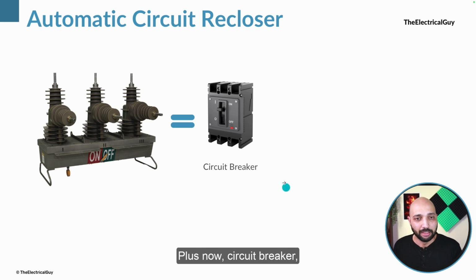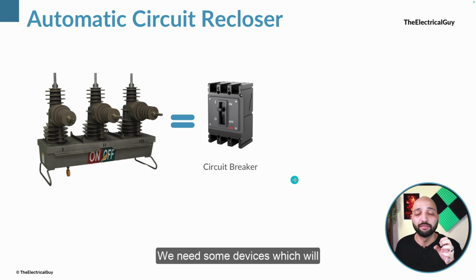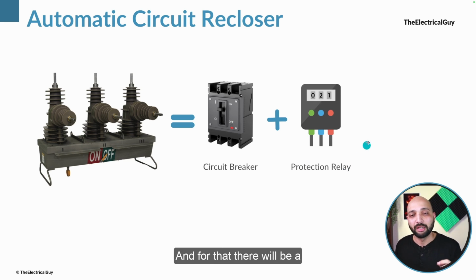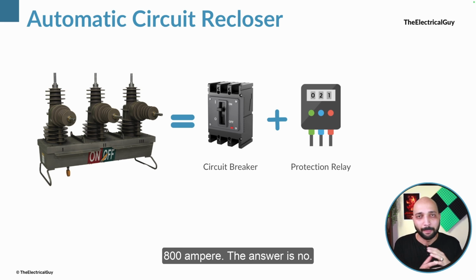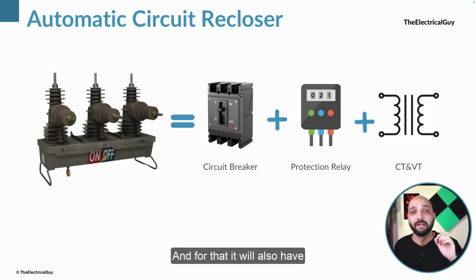Plus, now circuit breakers, are they capable of sensing the abnormal condition on their own? The answer is no. We need some devices which will sense the abnormal condition in the circuit, right? And for that, there will be a protection relay which will sense the abnormalities in the system. Again, the question is whether the relay that we will be using is capable of taking the input of high voltage like 12 kV or 24 kV, or maybe the high current like 1000 ampere, 800 ampere. The answer is no. We first need to lower down the values of voltage and current, and for that it will also have a current transformer and voltage transformer which will lower the values so that we can give inputs to the relay, and then the relay will give inputs to the circuit breaker. So everything put together is what is our automatic circuit recloser, right? Understood? A very useful device.